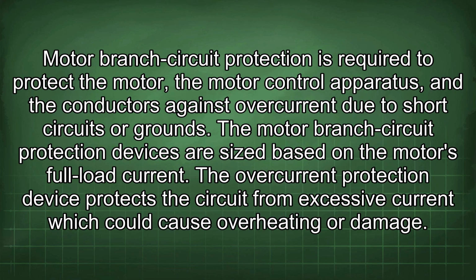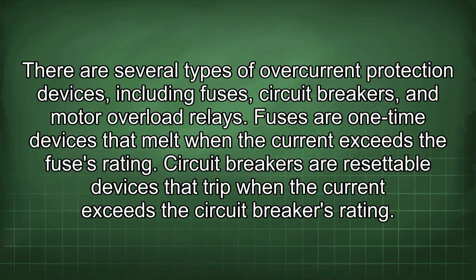Motor branch circuit protection is required to protect the motor control apparatus and the conductors against overcurrent due to short circuits or grounds. The motor branch circuit protection devices are sized based on the motor's full load current. The overcurrent protection device protects the circuit from excessive current which could cause overheating or damage. There are several types of overcurrent protection devices, including fuses, circuit breakers, and motor overload relays. Fuses are one-time devices that melt when the current exceeds the fuse's rating. Circuit breakers are resettable devices that trip when the current exceeds the circuit breaker's rating.